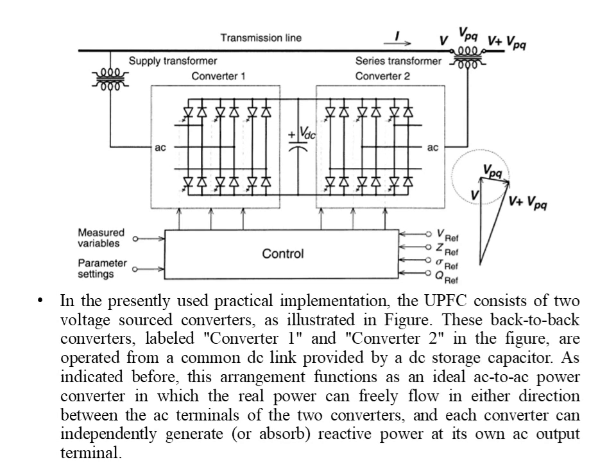In presently used practical implementations, the UPFC consists of two voltage source converters — Converter 1 and Converter 2 — as illustrated in the figure. These back-to-back converters are operated from a common DC link provided by a DC storage capacitor. This arrangement functions as an ideal AC-to-AC converter in which real power can freely flow in either direction between the AC terminals of the two converters.